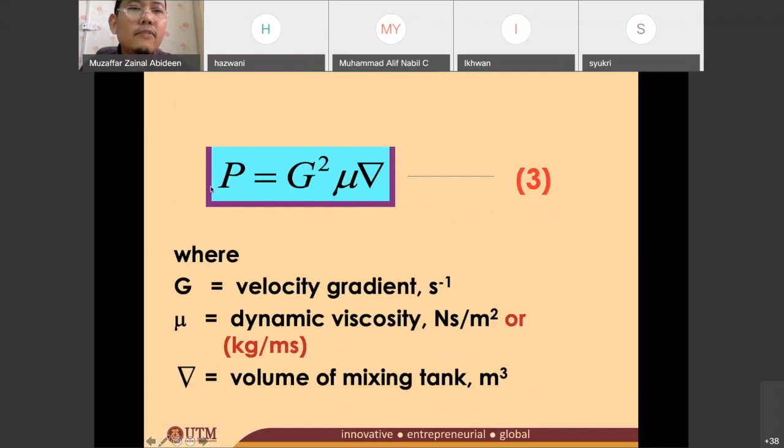And then another formula for P is equal to G squared mu V. G squared is velocity gradient, you know it just now. And mu is actually the dynamic viscosity, it is the property of the water itself. The dynamic viscosity and V, this kind of V or this triangle, I call it this is a V, is the volume of the tank. The volume of the flocculation tank. The isipadu or volume of the tank.